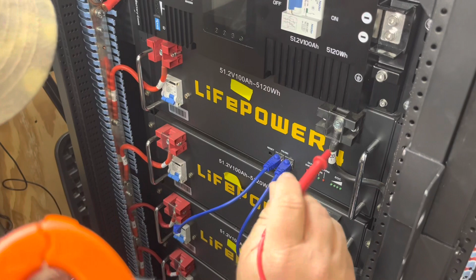Now, one more thing. We are going to torque this down to the specification, because that is important. A proper torque is very important. You don't want it under torqued. You don't want it over torqued, because an over torqued connection can create just as much heat problem as an under torqued connection. And that's even more important when you go over to the other bars, the copper bars, because the copper thread is softer than the steel. So if you over torque it, you're liable to strip it out. But anyway, let us get busy.